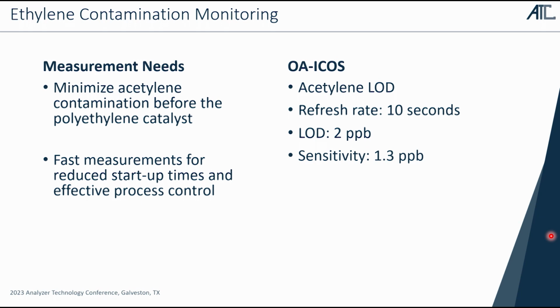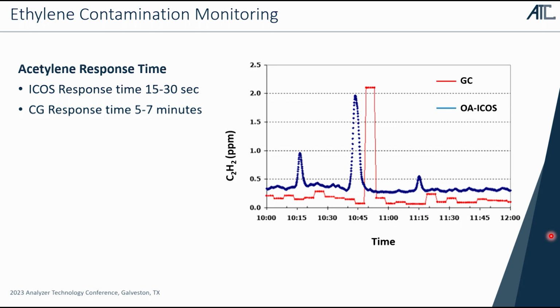So with acetylene, the analyzer has a refresh rate of 10 seconds. There's a T90 involved there, and that would depend on, obviously, the volume of the sample handling system bringing the sample in. But the analyzer itself refreshes in 10 seconds. And here you can compare the time advantage compared to a very well-established technique, gas chromatograph, which everyone trusts. It's very accurate, it's very sensitive, it's a great analyzer. We make those too. So I don't want to trash GCs by any means, but you can see the time advantage here. We're talking seconds measurement versus a few minutes.